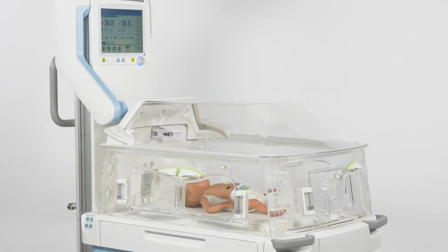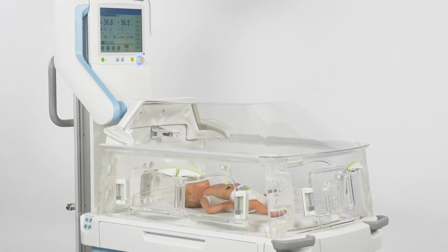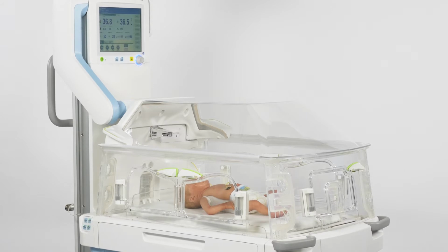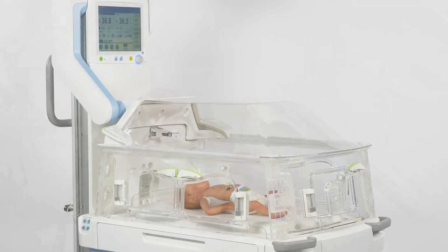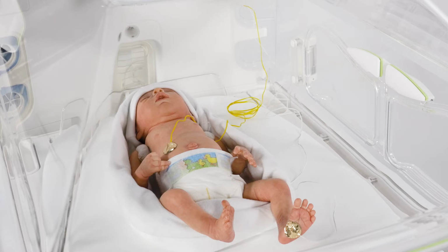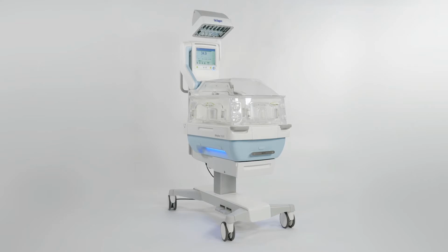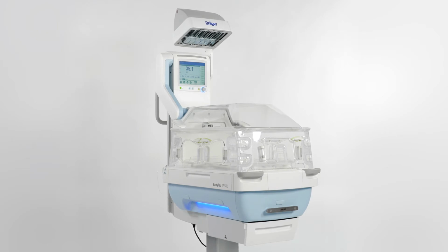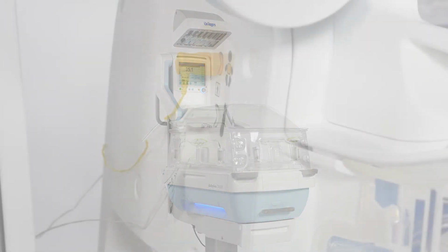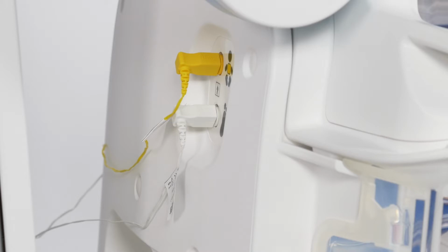The Weaning mode provides the possibility to automatically wean the baby from the incubator by gradually reducing the air temperature in intervals. The skin temperature is measured to check if the patient can maintain the required skin temperature on his or her own. If the patient is able, the air temperature is reduced to the next step. If the patient is unable, the patient compartment is heated back up to the air temperature that was in effect before. An alarm will be triggered in this scenario. To begin this mode, the device has to be in incubator operation and the yellow skin temperature sensor, which measures central skin temperature, needs to be connected.